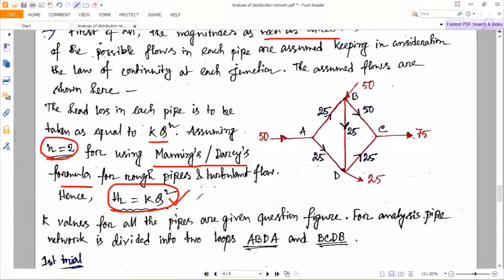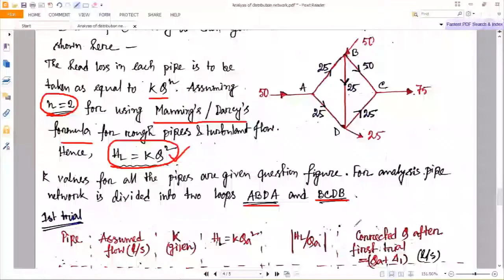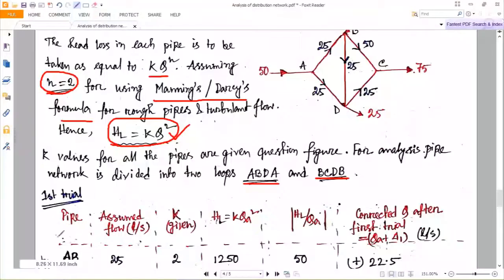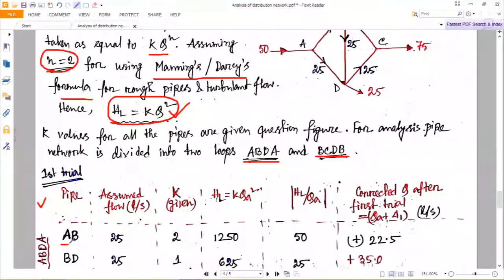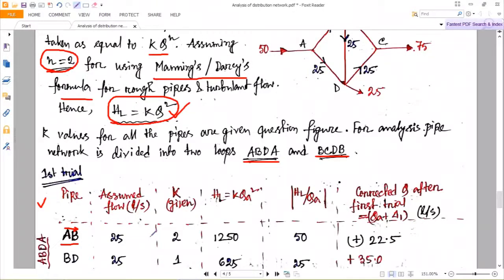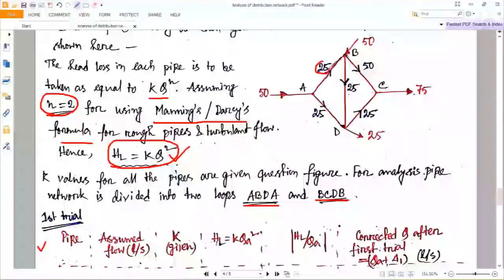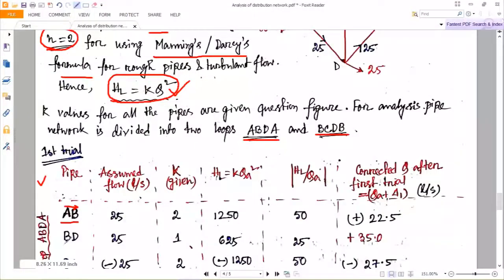For loop ABDA, three pipes are connected: AB, BD, and DA. Always the direction matters. Create a table with headings: pipe, assumed flow, k value, h_L, mod value of h_L/Q_a, and corrected flow after the first trial. For pipe AB, the assumed flow is +25 because the direction is from A to B. For pipe BD, the direction is from B to D, so it is also +25. For pipe DA, the flow was assumed from A to D as 25, so in the direction D to A it will be −25.